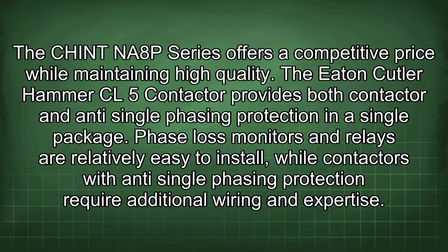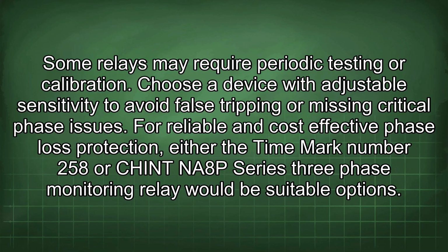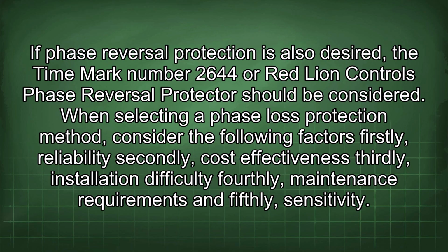Phase loss monitors and relays are relatively easy to install, while contactors with anti-single phasing protection require additional wiring and expertise. Some relays may require periodic testing or calibration. Choose a device with adjustable sensitivity to avoid false tripping or missing critical phase issues. For reliable and cost-effective phase loss protection, either the Timemark number 258 or Chint NA8P series 3-phase monitoring relay would be suitable options. If phase reversal protection is also desired, the Timemark number 2644 or Red Lion Controls phase reversal protector should be considered.